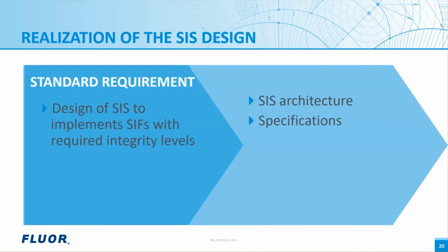The next step is to develop the specifications, ensuring they cover requirements such as hardware fault tolerance, behavior on detection of faults, diagnostic capabilities, and maximum allowed processor cycle time. Also ensure to cover requirements of cybersecurity. We have seen major cyber attacks on the control and safety systems in the recent past. The specifications for the field instrumentation should include the operational and environmental conditions. And for the valves, opening or closing time and the partial stroke test requirements are some of the important points to be taken care of.